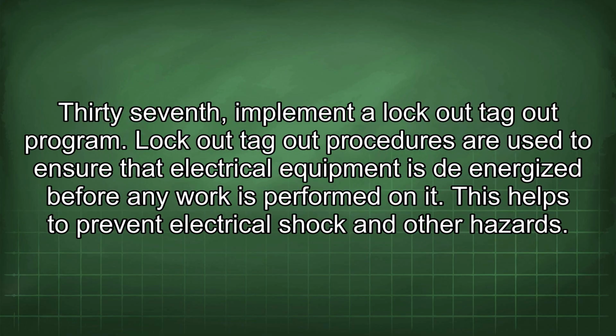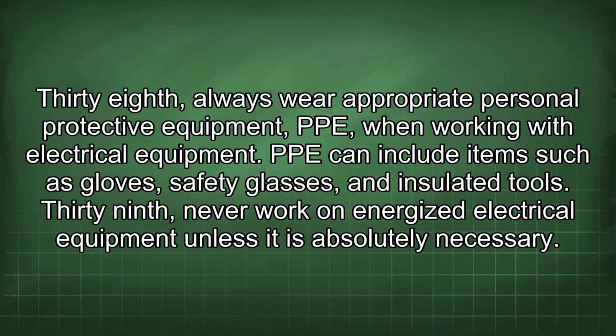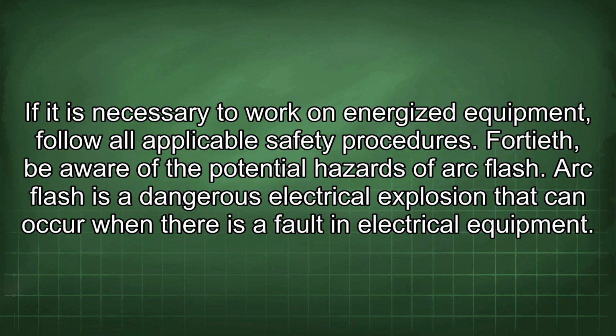37th, implement a lockout-tag-out program. Lockout-tag-out procedures are used to ensure that electrical equipment is de-energized before any work is performed on it. This helps to prevent electrical shock and other hazards. 38th, always wear appropriate personal protective equipment, PPE, when working with electrical equipment. PPE can include items such as gloves, safety glasses, and insulated tools. 39th, never work on energized electrical equipment unless it is absolutely necessary. If it is necessary to work on energized equipment, follow all applicable safety procedures.